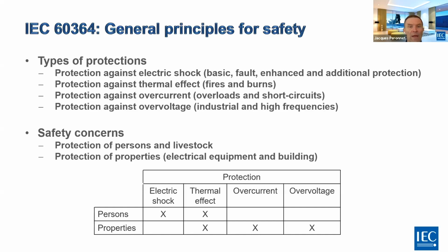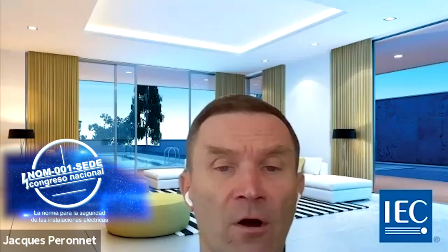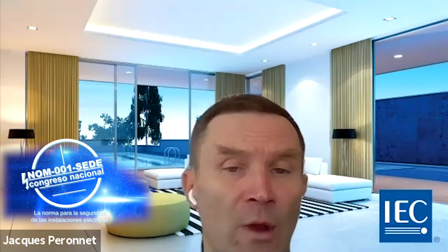In this part 4, as I explained to you, we cover the different types of protection. Regarding electric shock, we are going to cover what we call basic protection, fault protection, and enhanced and additional protection. For protection against thermal effects, we are going to cover fire and burns. Overcurrent, we are going to protect against overload and short circuits. And overvoltage, we are going to cover the industrial and high frequencies. Regarding safety, we are going to protect either persons and livestock and or protection of property. So that means the electrical equipment and the building.